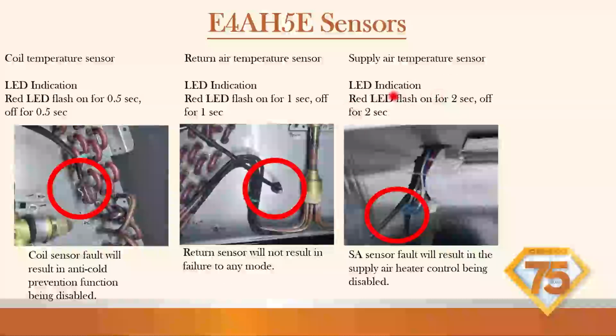Supply air temperature sensor, again, it's going to have its own separate red LED flash. Anytime we see red flashing, it usually indicates an alarm. Flash on 2 seconds, off 2 seconds. A supply air sensor fault will result in the supply air heater control being disabled.